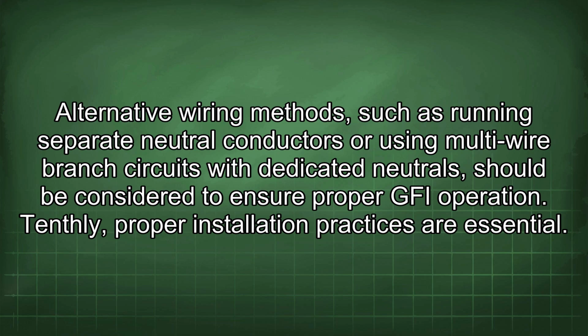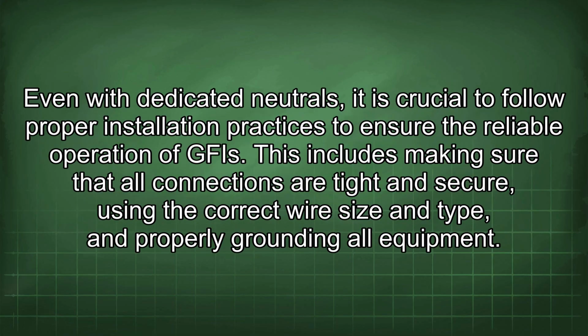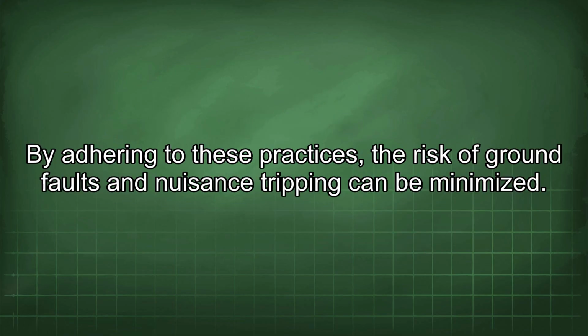10. Proper installation practices are essential. Even with dedicated neutrals, it is crucial to follow proper installation practices to ensure the reliable operation of GFI. This includes making sure that all connections are tight and secure, using the correct wire size and type, and properly grounding all equipment. By adhering to these practices, the risk of ground faults and nuisance tripping can be minimized.